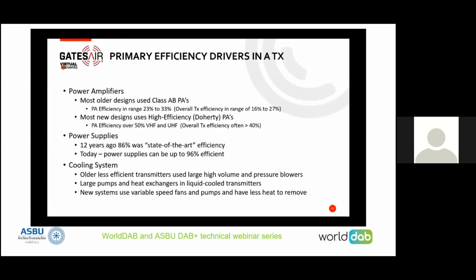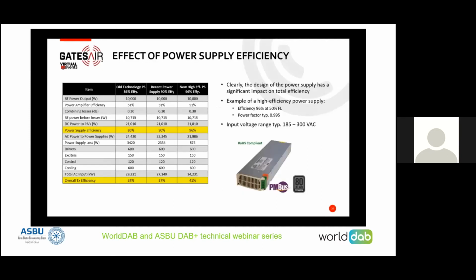Not that long ago, 86% was state-of-the-art efficiency. Over the past several years, using power supplies we pioneered into the broadcast space, we can achieve 96% AC to DC efficiency, and I'll give an example of how that makes a big impact in the transmitter. Cooling systems, with the right size pumps and blowers and heat exchangers, also allow the best energy efficiency solution.